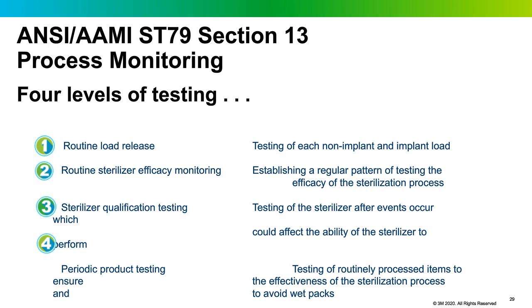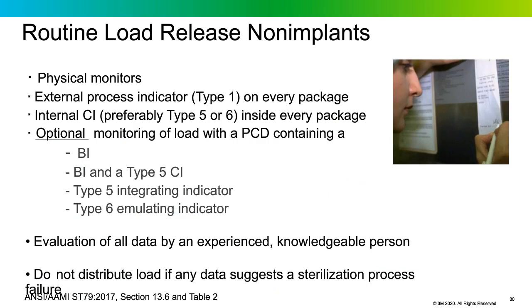Routine load release for non-implant loads uses a variety of monitoring tools. The decision to release a load is based on physical monitors, the Type 1 process indicator on every package, an internal chemical indicator inside every package, and optionally a process challenge device containing a BI or a Type 5 CI. All that data is evaluated by an experienced person. If anything indicates a problem, we declare a sterilization process failure, investigate, and reprocess those load items.